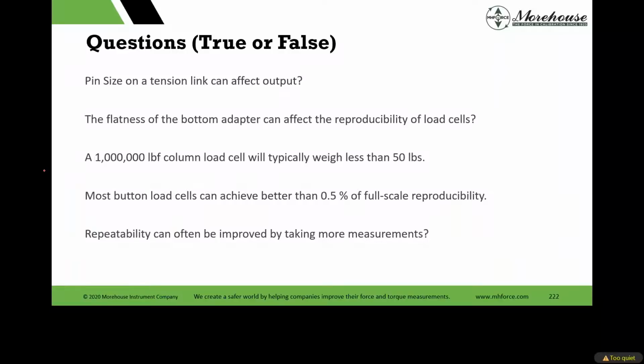So let's play along. I'm up for true, false, or whatever, but: pin size on a tension link can affect output. True, right? Remember the extreme, the pin size, the 1.72% error on the 50,000 pound device. And then I showed you the 13 out of 24 measurements were not in, just by rotating the pins.